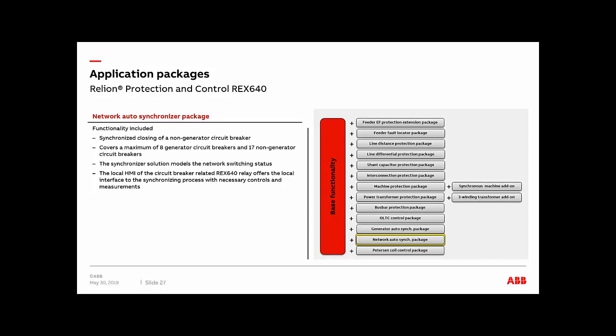So pretty much in this one, it is important to point out that the prerequisite is that all the feeders in the system where you want to implement this auto synchronizer logic need to be equipped with REX640 relays. It has to be this way so the relay can work with the other 640 devices as well. And important also to mention here that the information exchange between the 640s for this application is going to be mainly IEC 61850. It could be binary and analog as well, depending on how you implement your scheme. But you do need communication through GOOSE using IEC 61850. So that's one thing that's important to mention if you want to implement this type of system.